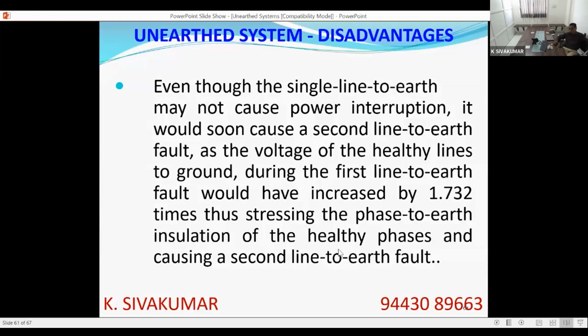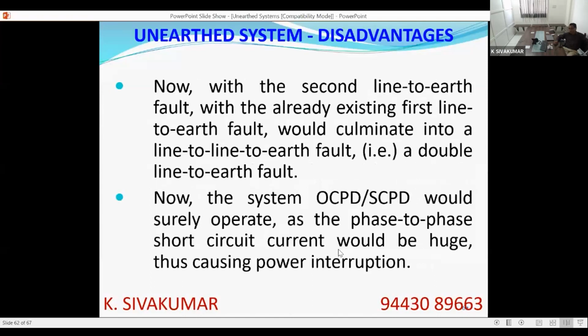So a second line to ground fault will soon occur, as the voltage of the healthy line to ground during the first line to ground fault will have increased by √3 times. Thus, the phase to earth insulation of the healthy phases is stressed now, because the voltage has increased. So sooner than later, there will be a second earth fault. Whenever a second earth fault happens, the fault is no more a single line to earth fault. It is a double line to ground fault, we call.